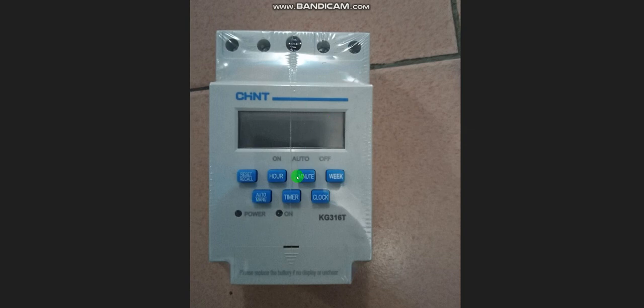You set this module to control gen 1, and also set this one to control gen 2. Once it is morning, depending on the time set, it will send a signal for gen 1 to come up. Gen 1 will work for a specific time, then shut down. Then another one of these will activate gen 2. So use this module controller, the calendar timer, to interface the two sources of power.